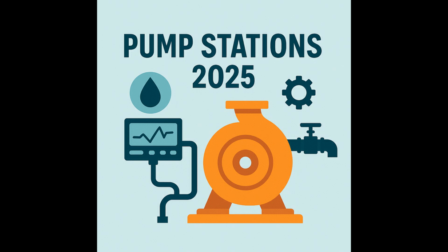Makes sense. However, sometimes mixing pump types or hybridization is done. This might happen when a station has to handle vastly different flow conditions very efficiently. For example, you might have one smaller pump optimized specifically for very low overnight flows to save energy, and then larger pumps designed just for handling high peak flows during the day or storm events. So more complex, but potentially more efficient overall. Potentially, yes, but it definitely adds complexity to operations, maintenance, and controls. So standardization is usually the preferred route unless there's a very compelling efficiency case for mixing types.